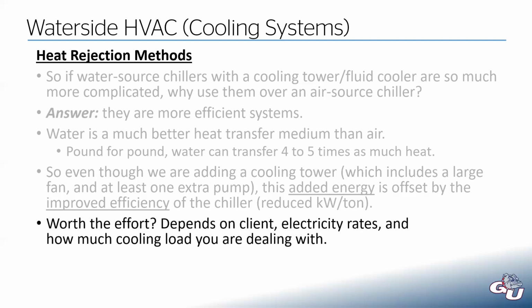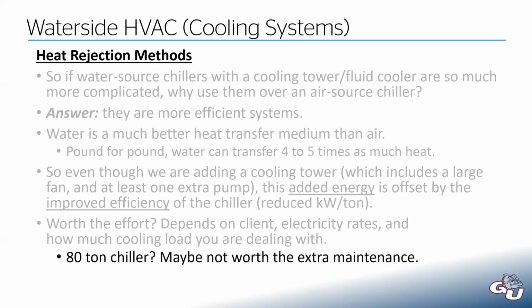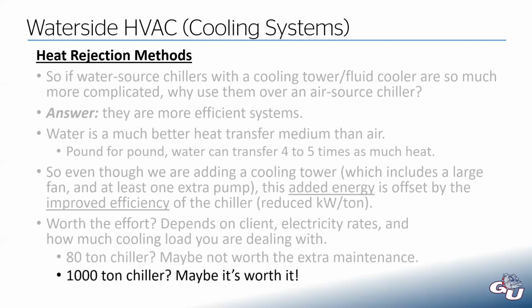And is that worth the effort? Depends on a number of things. Depends on your client. What are your electric rates? How much cooling load are you dealing with? If you have an 80-ton chiller, that would be a pretty small chilled water system. Putting in a water source chiller with a cooling tower, that probably doesn't make a lot of sense. But if you have a big 1,000-ton chiller, it's moving all kinds of energy, maybe that would be worth it to maintain that extra equipment.